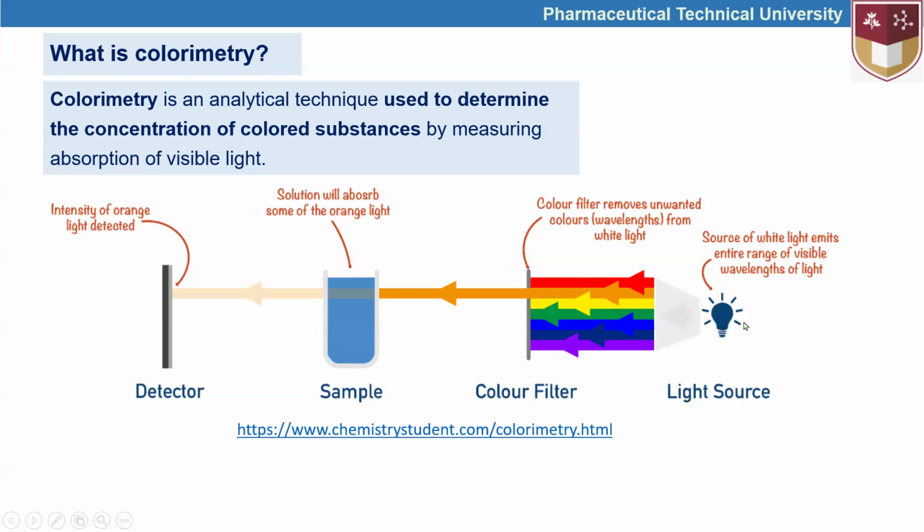There is the source of the light, which is filtered by some filters, and the filtered spectrum of the light is absorbed through the samples, and the transmitted light is identified by the detector photocell. So then the transmitted dose of the light is used to define the concentration of the compound that absorbs the light. This is how the colorimetry works.